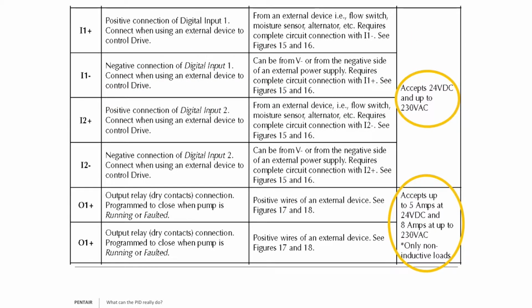Now, when you look at the inputs, understand that the inputs can accept 24 volt DC all the way up to 230 volt AC, so 115 or 230 volt. An input is simply looking for voltage, is all it's doing. Not load, just for a signal. Once it sees a signal, then you answer the question: when I energize this circuit, I want A, B, or C to work. Meaning tell it to stop, tell it to run, or tell it to look at a different set point for pressure.